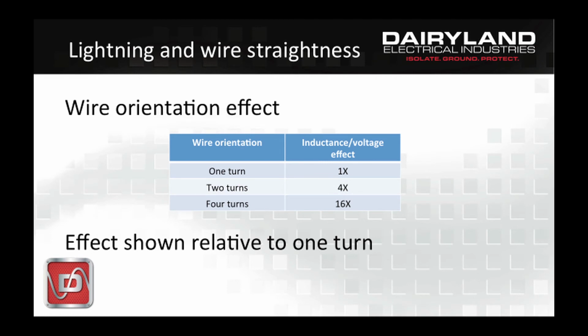Now back to orientation. Here's a comparison of the number of turns in a wire and the resulting inductance, which leads to the voltage effects we're talking about. Note the difference between 1 turn of a wire, 2 turns, and 4 turns. You'll see that there's an exponential effect on inductance and therefore voltage for adding turns of wire. So we've shown this graph relative to 1 turn, but clearly these turns are detrimental in the sense of limiting voltage. These turns are useful if you consider other electrical properties of making a coil for an intended purpose. You're using the property of inductance to accomplish another effect.